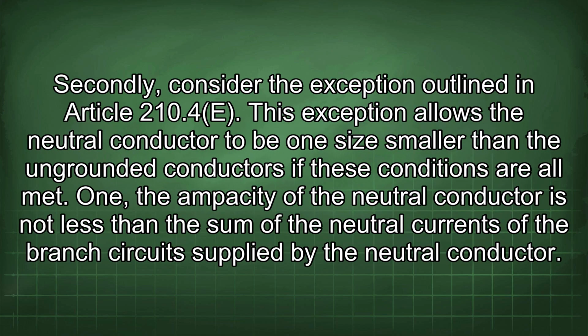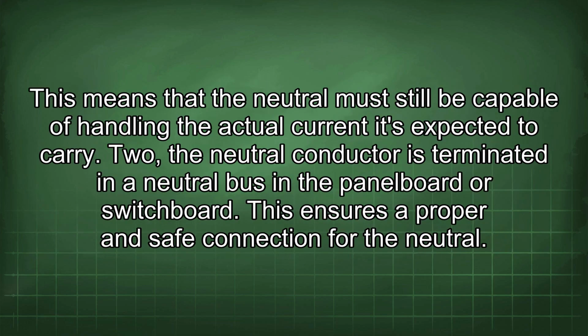Secondly, consider the exception outlined in Article 210.4(E). This exception allows the neutral conductor to be one size smaller than the ungrounded conductors if these conditions are all met. 1. The ampacity of the neutral conductor is not less than the sum of the neutral currents of the branch circuit supplied by the neutral conductor. This means that the neutral must still be capable of handling the actual current it's expected to carry.